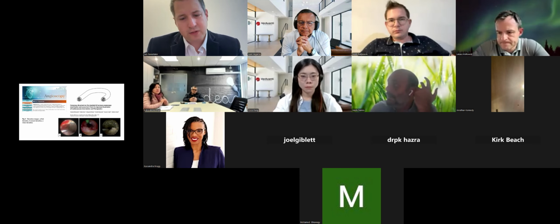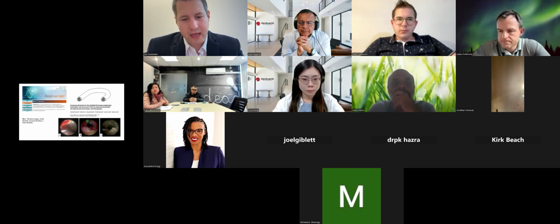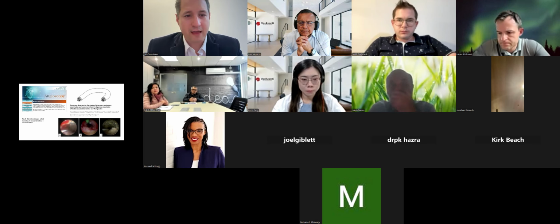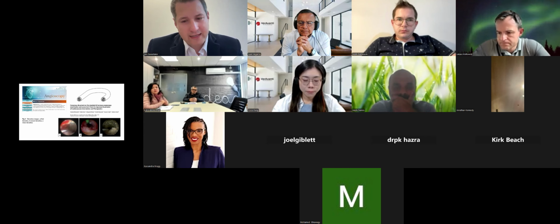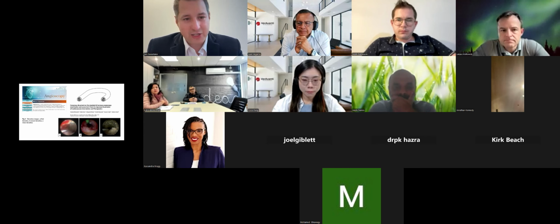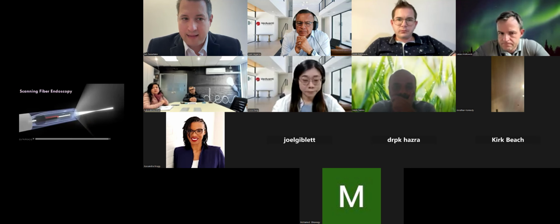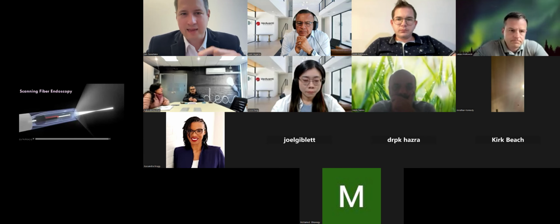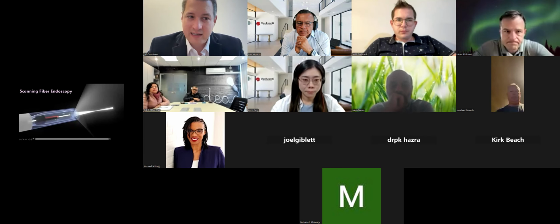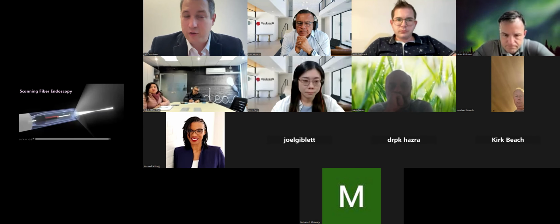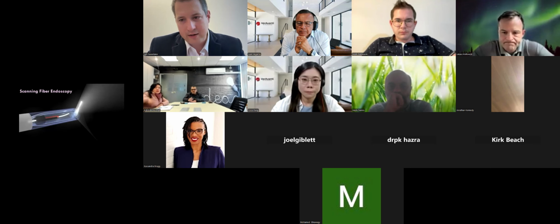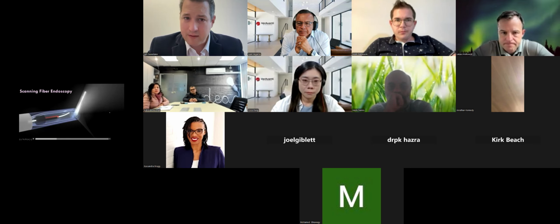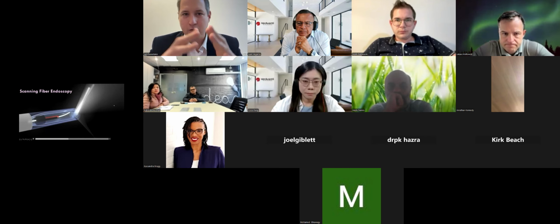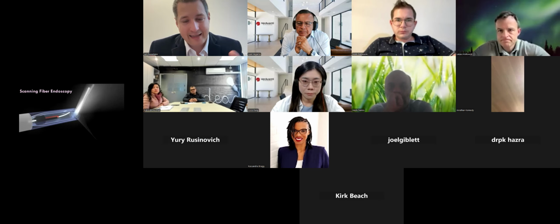And what Veravanti has done is develop a new type of imaging platform, in the way that you have ultrasound and X-rays and MRIs. Veravanti has developed a scanning engine for lasers. The way this works is they took a single optical fiber and developed a tiny micro machine that fits within a millimeter catheter, a 3 French catheter. That machine is a scanner that is spinning or scanning the optical fiber, which transmits a laser. The laser is scanning in front of the device. What you are seeing here is the concept of the laser beam scanning from the center and following bigger and bigger circles, and the light is projected forward.